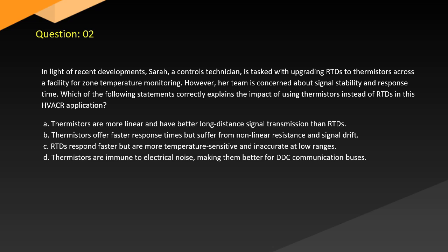A. Thermistors are more linear and have better long-distance signal transmission than RTDs. B. Thermistors offer faster response times but suffer from nonlinear resistance and signal drift. C. RTDs respond faster but are more temperature sensitive and inaccurate at low ranges. D. Thermistors are immune to electrical noise, making them better for DDC communication buses.